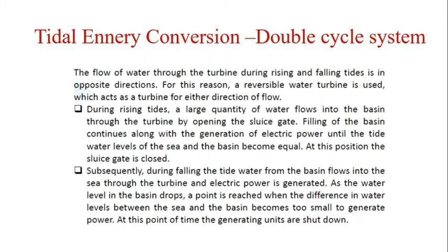During rising tides, a large quantity of water flows into the basin through the turbine by opening the sluice gate. Filling of the basin continues along with the generation of electrical power until the tide water level of sea and the basin becomes equal. At this position, the sluice gate is closed. Subsequently, during the falling tide, water from the basin flows into the sea through the turbine and electrical power is generated. As the water level in the basin drops, a point is reached when the difference in water level between sea and the basin becomes too small to generate electrical power. At this point of time, the generating units are shut down.